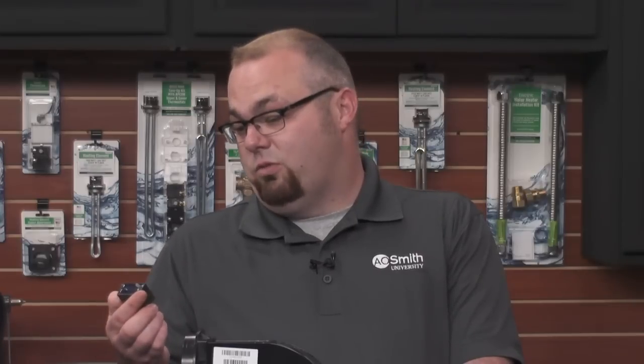You may not be able to go to your supplier and find one that looks exactly like this, but as long as you find one that's rated the same, this one I believe is rated 3 microfarads. Yes. If you find one that's rated the same, you could at least get the heater back up and running until you can get the correct one that fits, that tucks into the blower and looks nice.